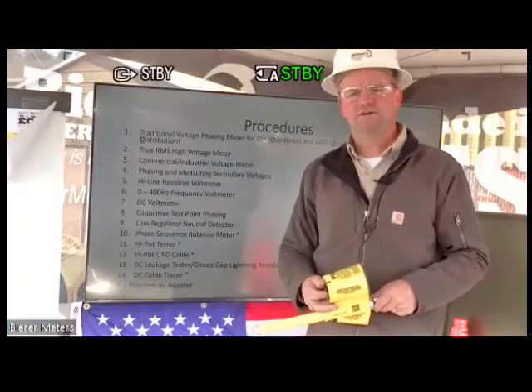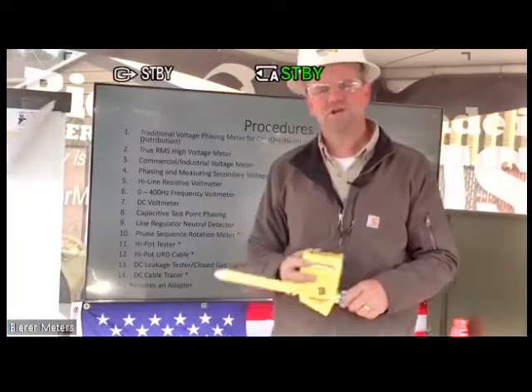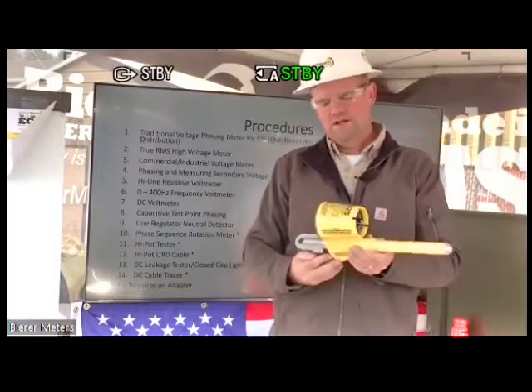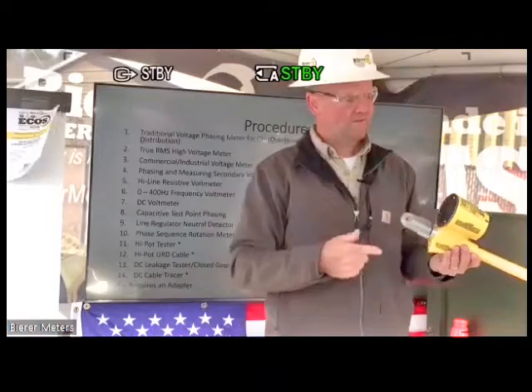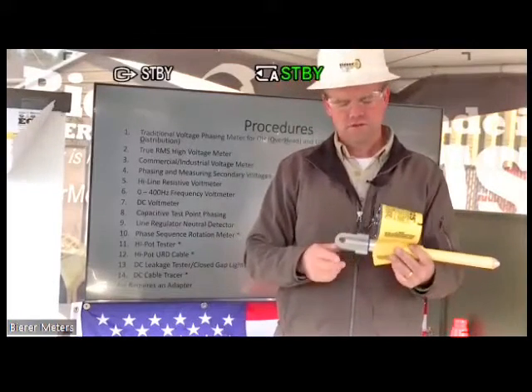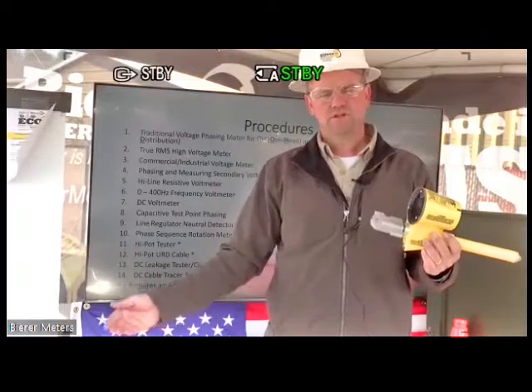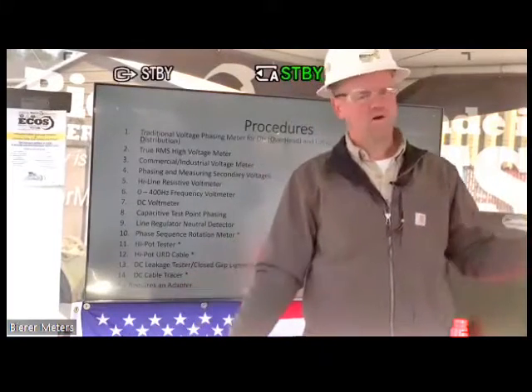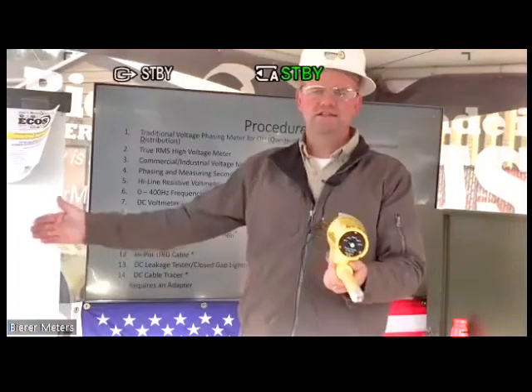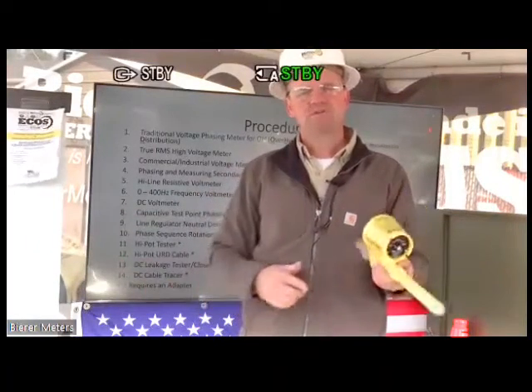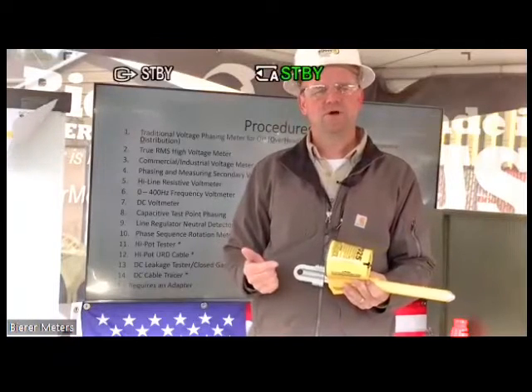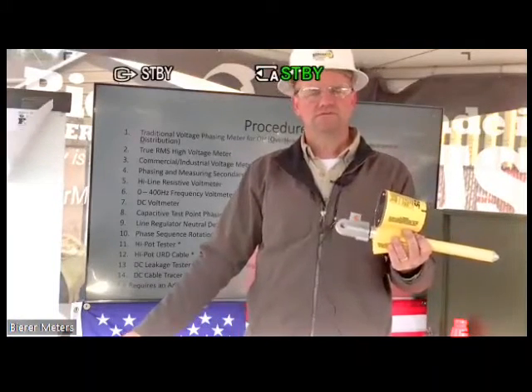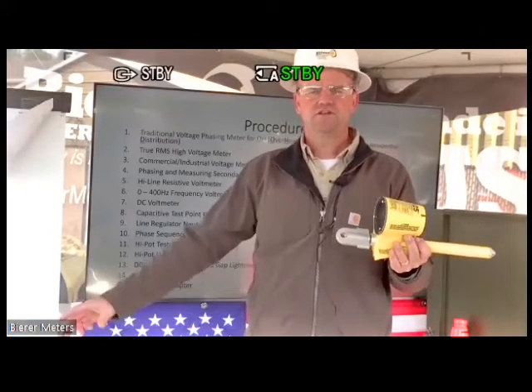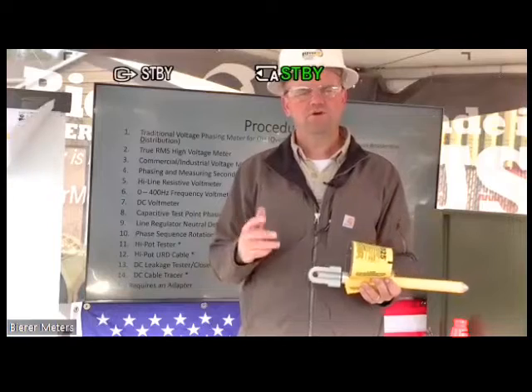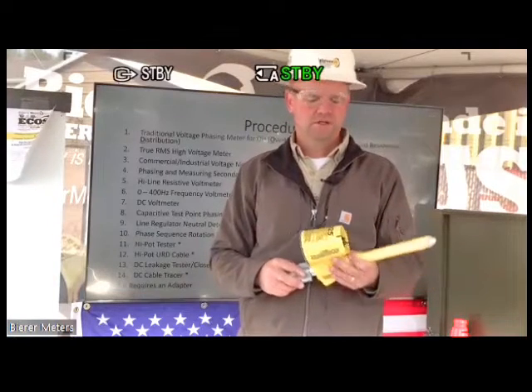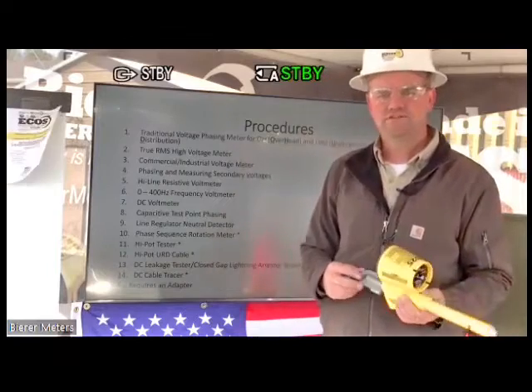A highline resistive voltmeter. So we do have some utilities that request this tool to be used where they have the interconnect cable attached to it, and we have this set up here, and we'll demonstrate that in a few minutes. But we have an interconnect cable attached to it with a ground clamp attached, and they just walk around with a 100-foot cable and they take readings. Okay, so that's a highline resistive voltmeter. You're not really utilizing the second probe. This cable just goes straight to ground. So again, it's a true RMS reading, but you're not utilizing that second probe. So we'll go over the pros and cons with doing that in just a few minutes, but you can use the tool for that task as well.